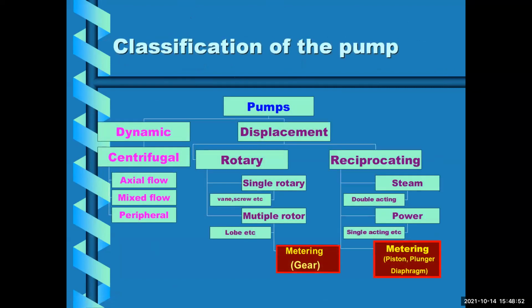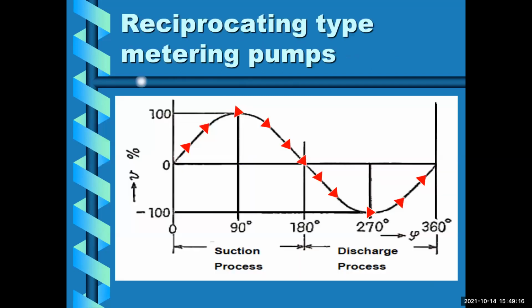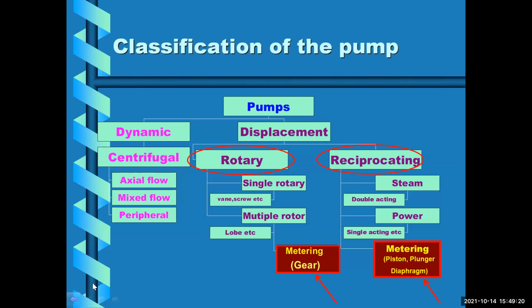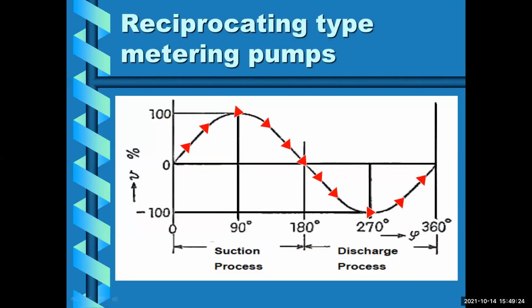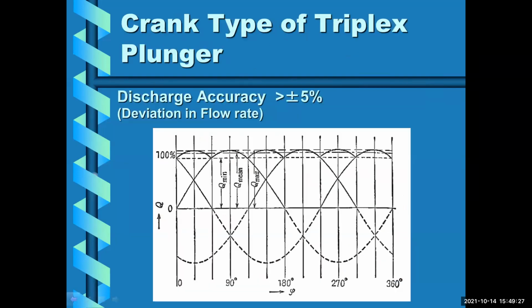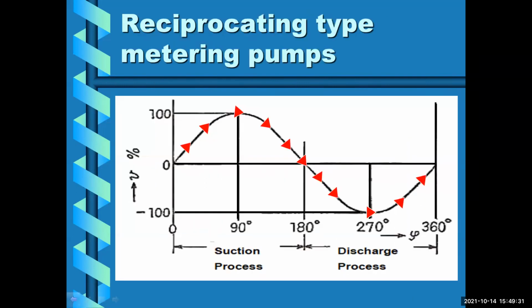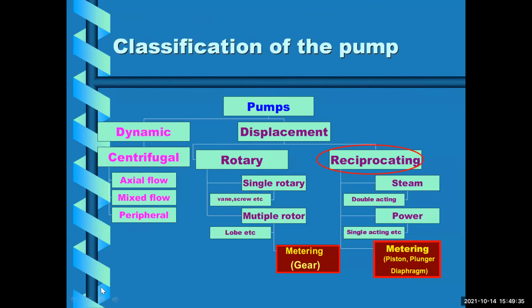Metering pumps are often the preferred choice of continuous flow applications. They are classified as reciprocating types, such as a piston, plunger, and diaphragm, or rotary type. A typical example is a gear pump. Their primary function is to accurately feed predetermined volume of a liquid into a process or system. In reality, pumping accuracy is different from one type to another. Selecting a pump for the application, the user must pay attention to properties such as metering accuracy and stability, as well as a level of pulsation.